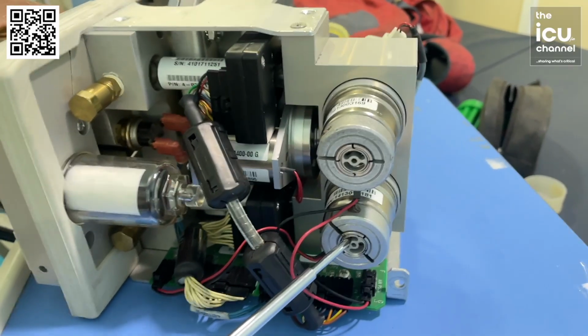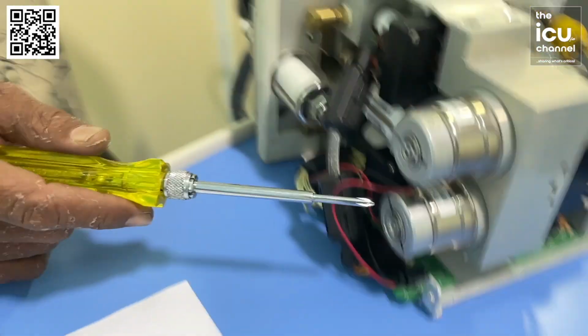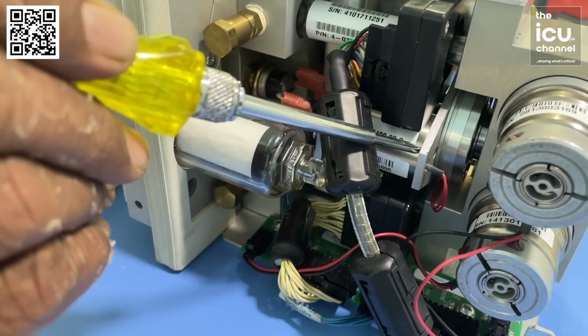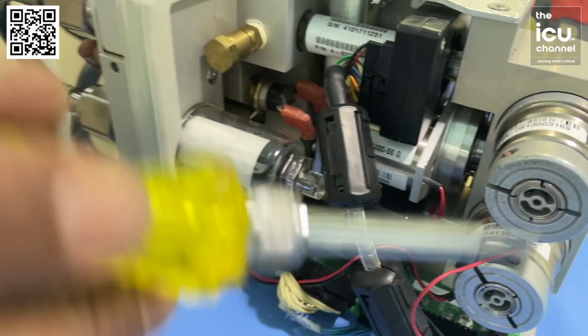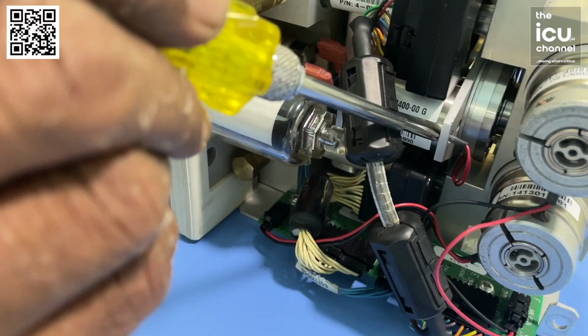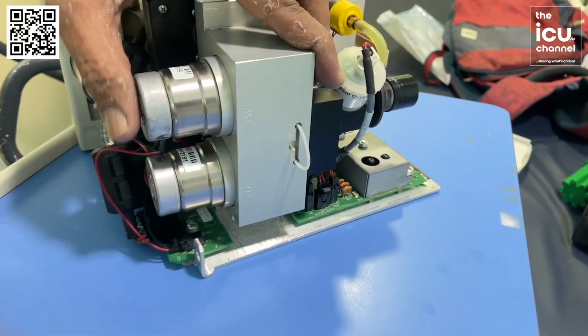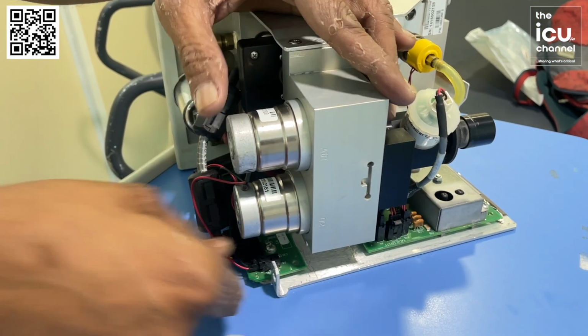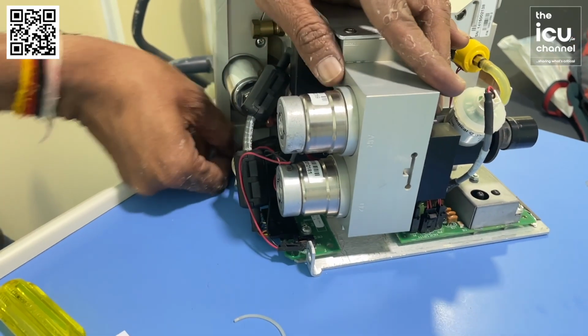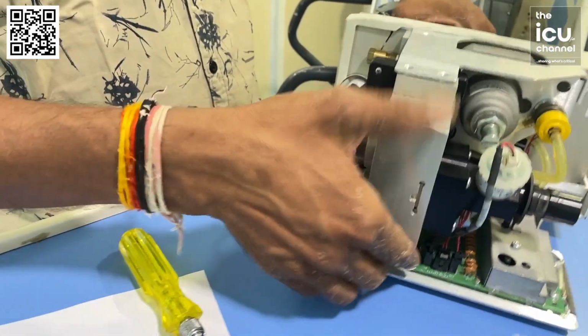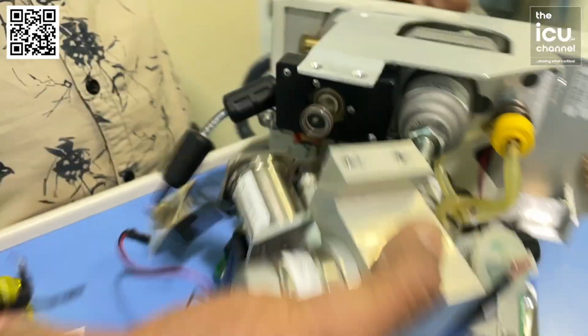Again the pressure is being checked whether it is coming in the correct quantity or not, and after both the pressures are checked, they get mixed, and after mixing it comes to the safety valve, which again checks whether the tidal volume and the pressure are correct or not. Once again a check is done. Now where they get mixed, this is the circuit in which both of them get mixed. So Pawan is opening up and will show where the medical air and the oxygen get mixed. Okay, so Pawan has now opened the mixing chamber where air and oxygen are getting mixed.